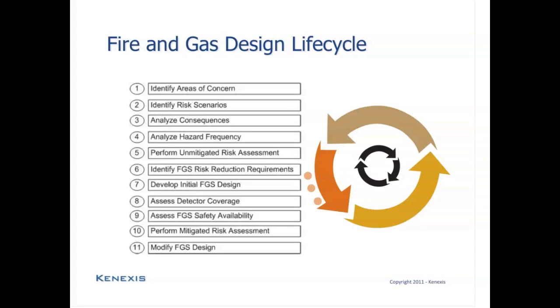For each of those scenarios, you're going to want to analyze what types of consequences can occur as the result of those hazardous events, and what the overall impact on the people and the facility would be if those consequences were to occur. In addition to the magnitude of the consequence, you're also going to want to be concerned with the frequency of the consequence. The more frequently a fire or a gas release will occur, the more rigorous and more effective the countermeasures or the risk mitigation system will need to be.